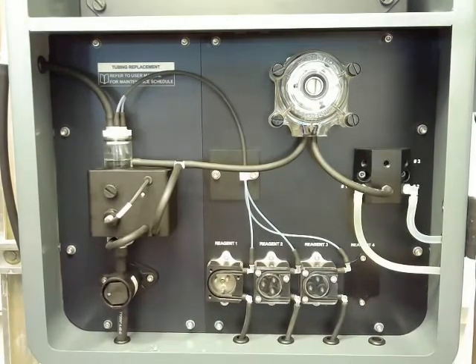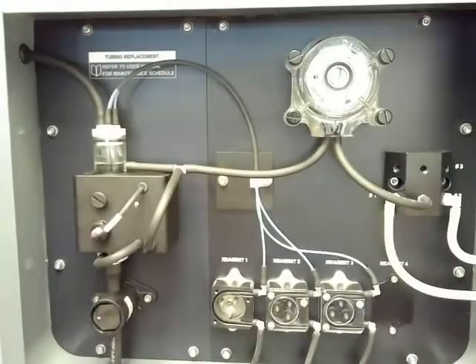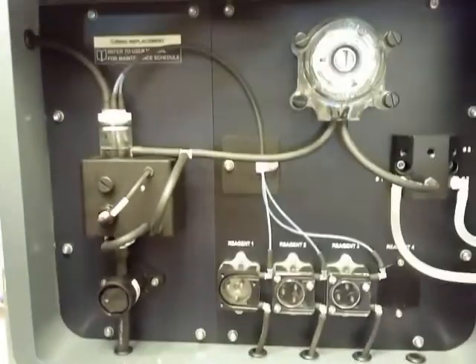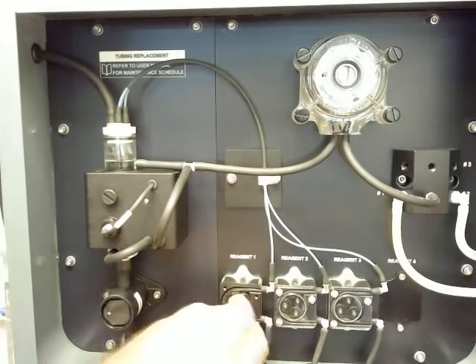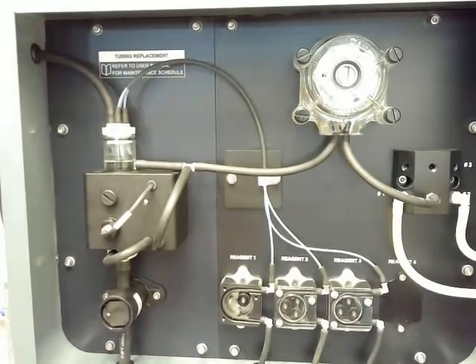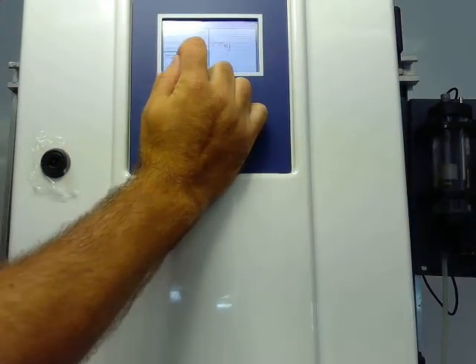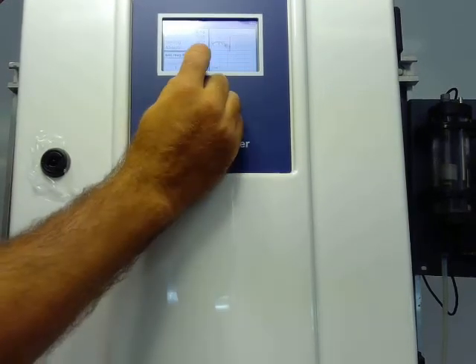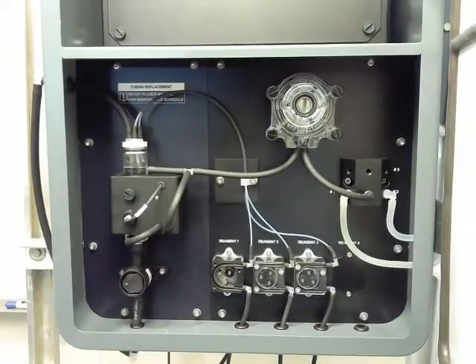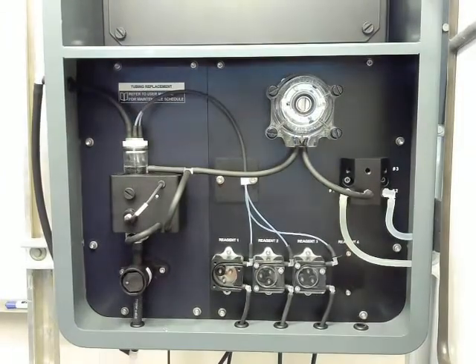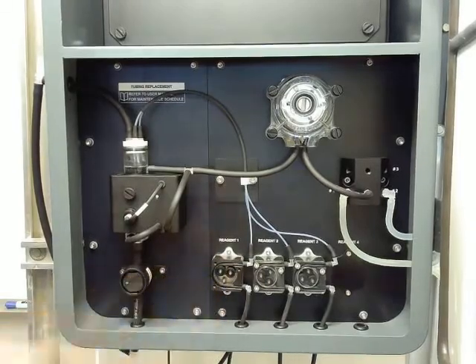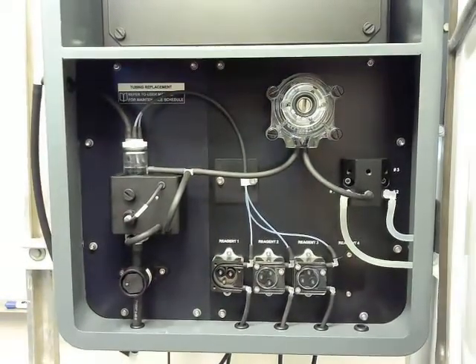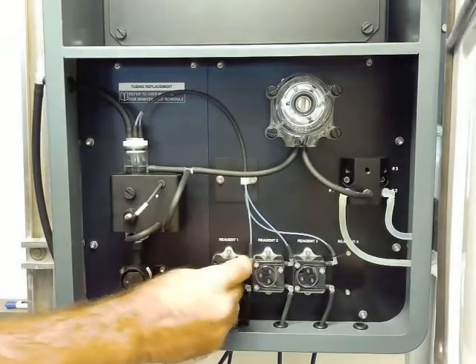So to get these rollers back into place, we should see on our pump we've got our 3 roller places. There should be about one open one that we can slide that pump onto easily. And then we'll want to come back to our main screen where we have our manual commands list. And we'll pick the same one that we would use for a prime. So we go to add reagent 1, just do it for 1 second, and then hit on. And when I hit on, you'll see that roller should rotate into place, and we should free up the next roller's position. So for 1 second, now we've got next roller position, put that roller into place, and then do the same thing again. 1 second, and get the last roller into place there.